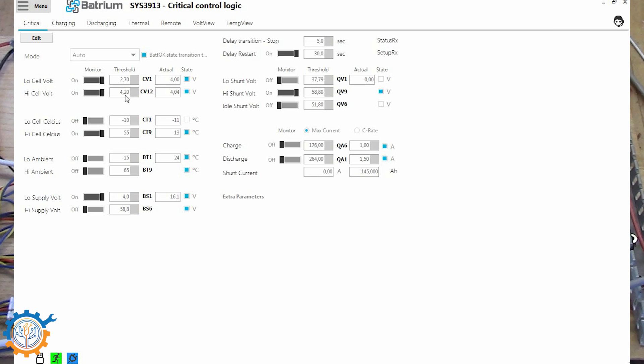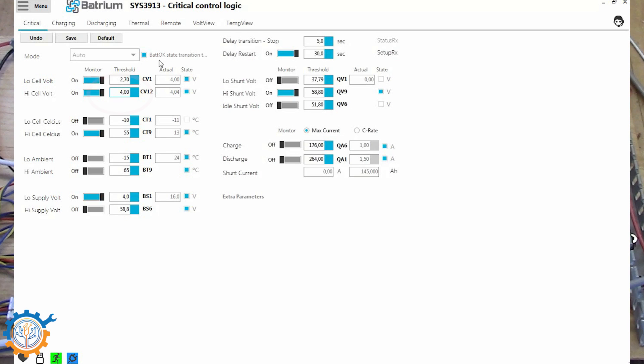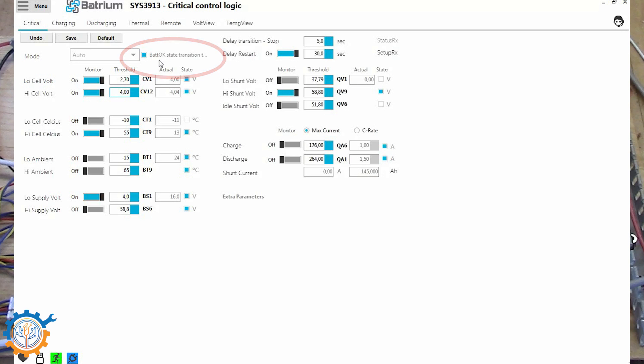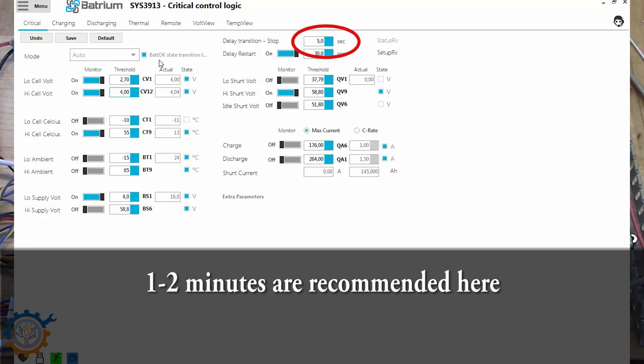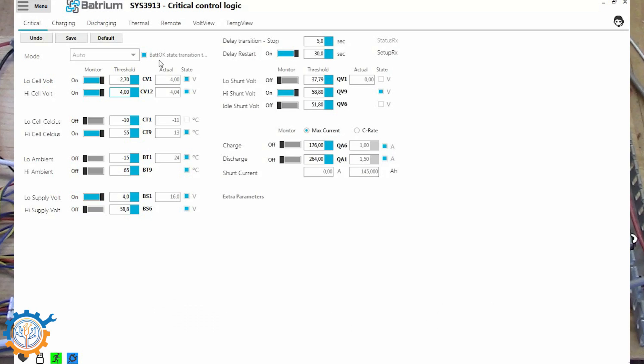Let's go to edit. And as we can see the actual voltage is 4.04 volt. So let's change the threshold to 4 volt. And as you can see up here, we have the battery ok state. It should take, as soon as I press save, it should take roughly 5 seconds to actually go into the next state. And that's defined here. You also have a delayed restart, and that is at 30 seconds. In a real scenario, the delay to go to a critical state should be 1 to 2 minutes depending on the setup. Save.